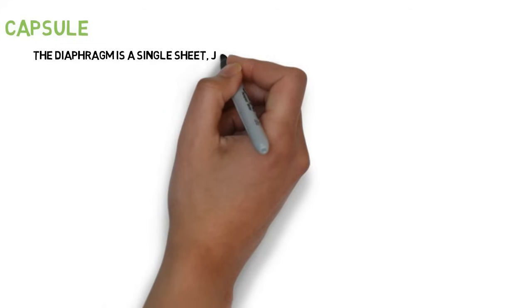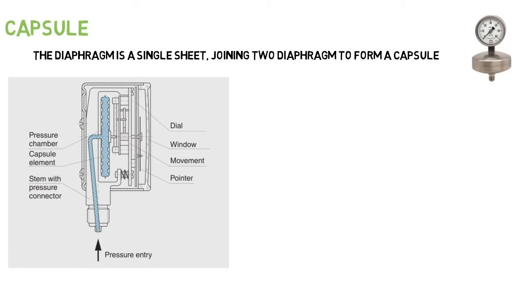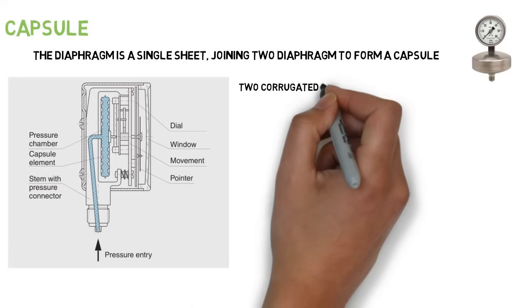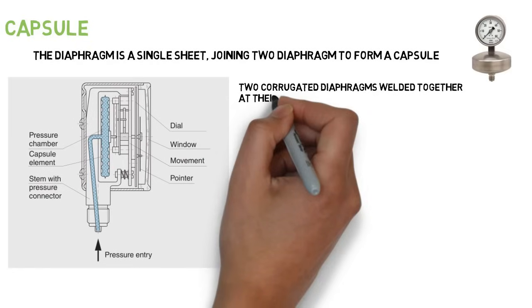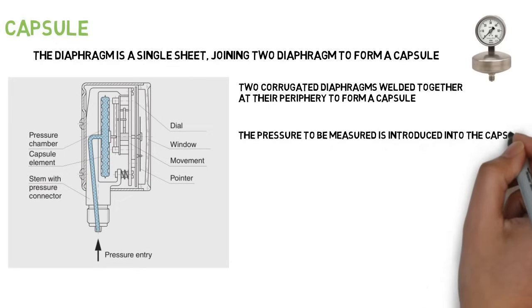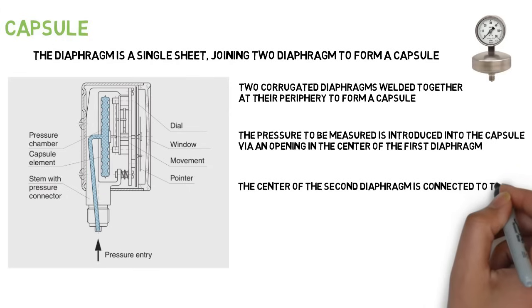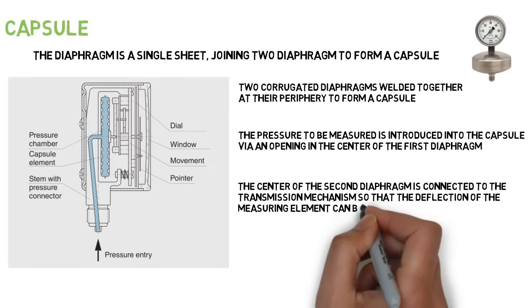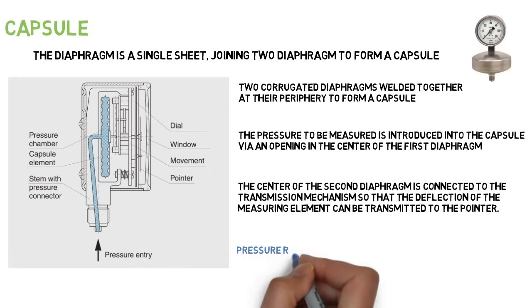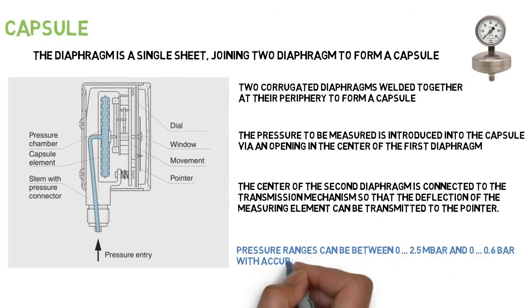Capsule. The diaphragm is a single sheet; joining two diaphragms forms a capsule. The sensing element of a capsule pressure gauge consists of two corrugated diaphragms welded together at their periphery. The pressure to be measured is introduced into the capsule via an opening in the center of the first diaphragm. The center of the second diaphragm is connected to the transmission mechanism so that the deflection can be transmitted to the pointer. Pressure ranges can be between 0 to 2.5 millibar and 0 to 0.6 bar, with accuracy classes of 0.1 to 2.5.